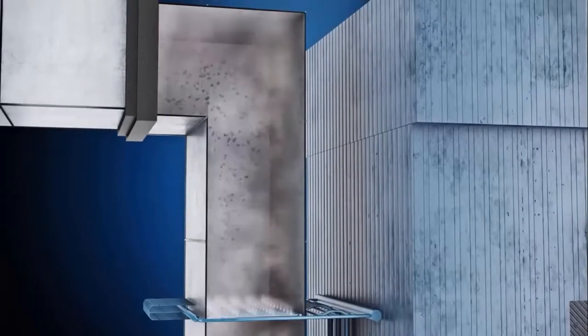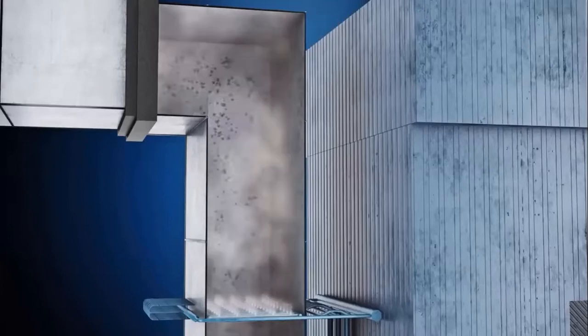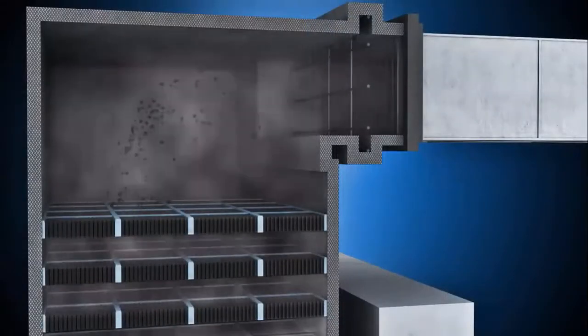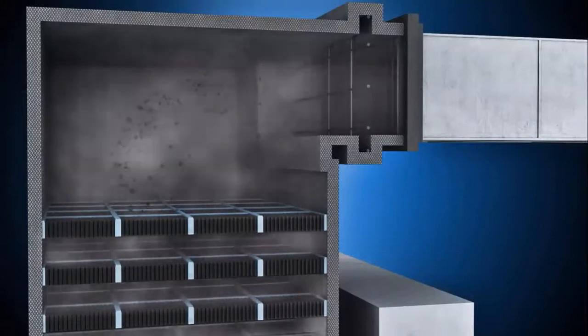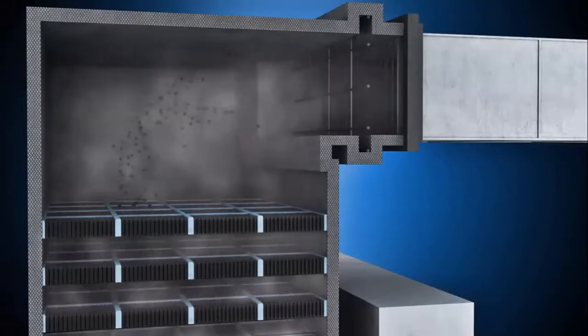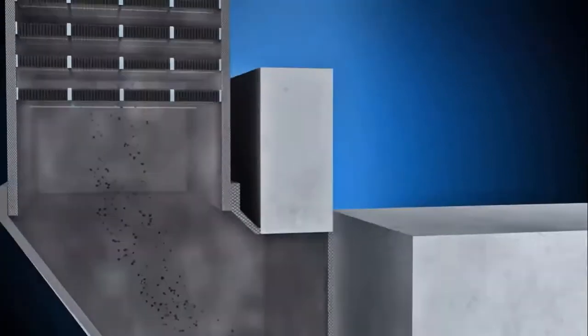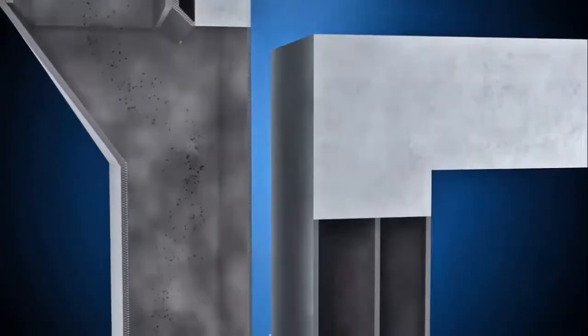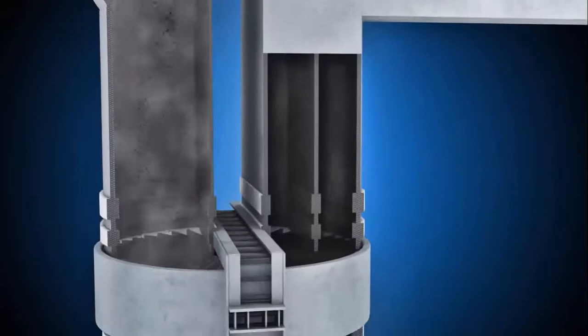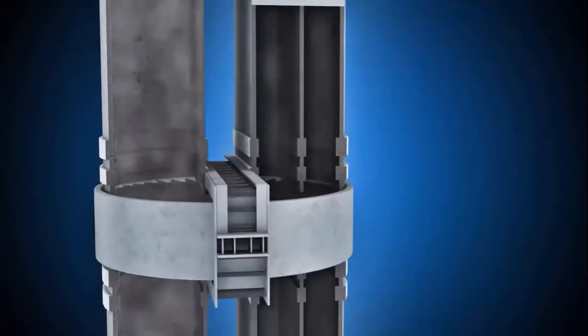SCR. While entering the SCR, ammonia is injected into the flue gas stream, where it reacts with several catalyst layers to reduce the nitrogen oxide compounds. The flue gas then passes across the air heater, where over 400 degrees of temperature are transferred from the exiting flue gas to preheat the primary and secondary air entering the plant.